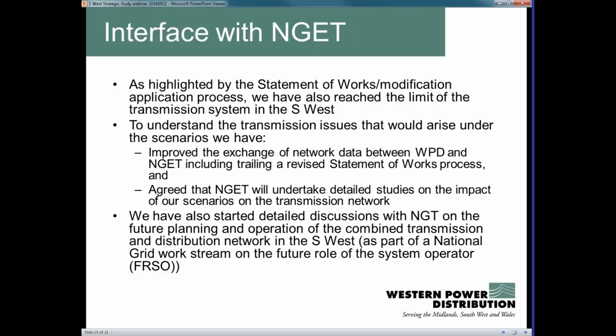I've mentioned the national transmission network a few times and the interface with National Grid. Between us we have commercial arrangements, and as part of that we tell National Grid when generation connects to our network, giving them the opportunity to assess whether that has any impact on their network - done via a process called Statement of Works. Where things are identified, there's a modification application process that follows. What's really come out of that process is that we've either reached or are reaching the limit of the transmission system in the southwest, and are having to increase things like active network management to accommodate further generation.